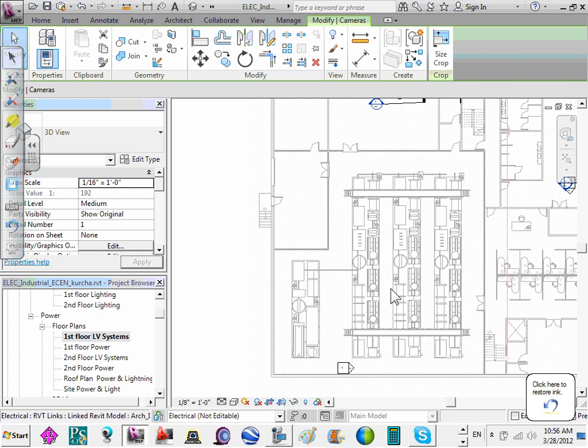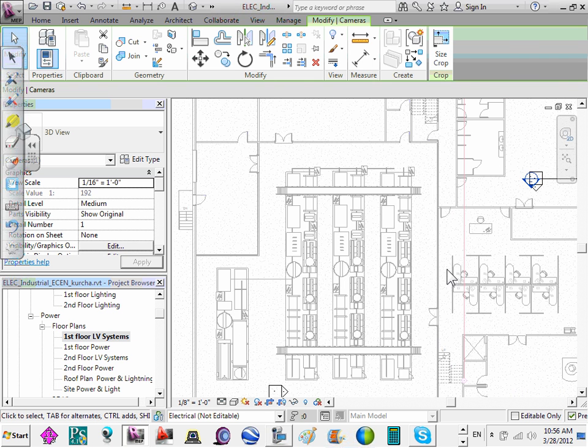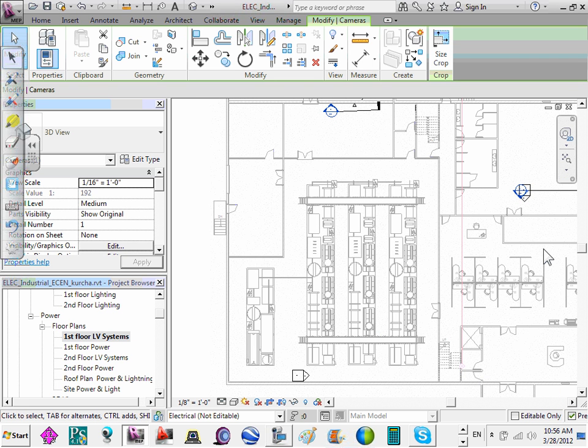Getting it. So if they're saying, okay, they want to put more detection in there, putting smoke detectors up in the ceiling, in the high ceiling, you're not going to get the detection that you want because of stratification. If you're going to put in detectors up here, depending on what the manufacturing is, you're going to have a lot of dust, and your system's just going to get dirty. So now we have two options, where before we used beam detectors as one.